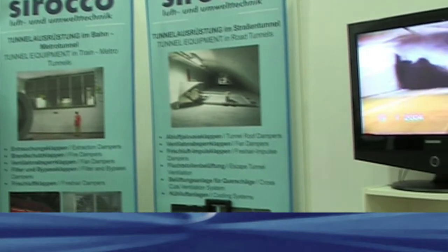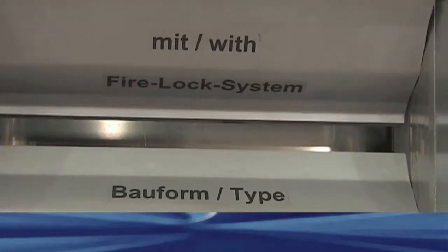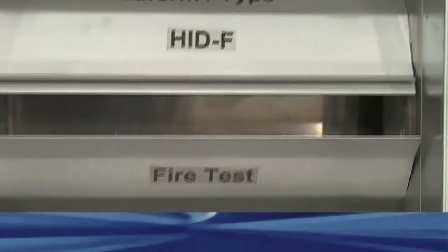Were serious tunnel fires the trigger for a new ventilation system? The development has actually started before the big fires, no matter if they occurred in Switzerland or Austria. One started from a distributed extraction with fixed lamellas, then moved to dampers. This concentrated type of extraction is much more efficient, if you are talking about extraction systems in general, than if it is spread.